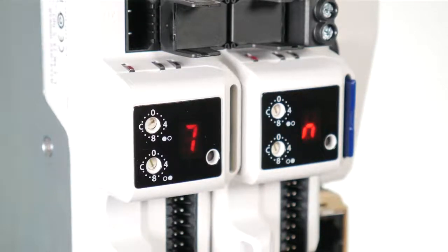The station alias or node address can be configured from the rotary dials of the KI compact display with no power applied to the drive, with the exception of zero value settings. Non-zero configured settings will then be transferred to the drive on the next power up. The KI compact display can be installed or removed while the drive is powered.